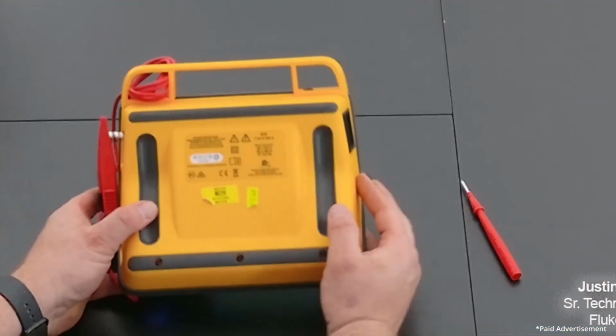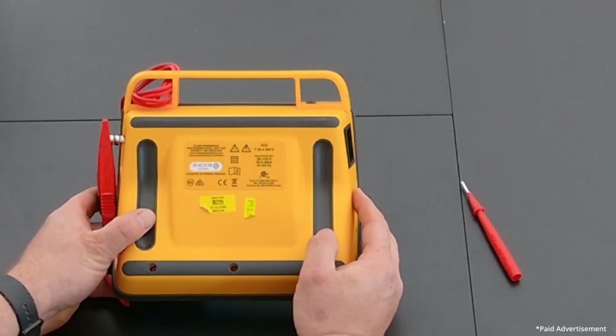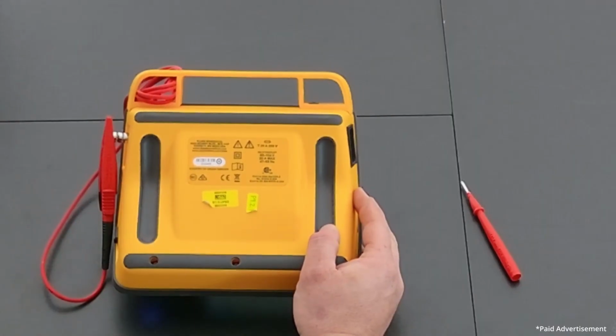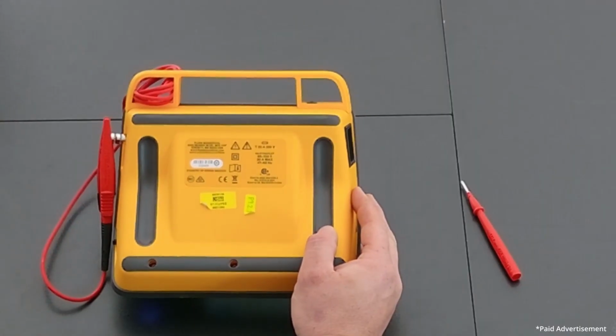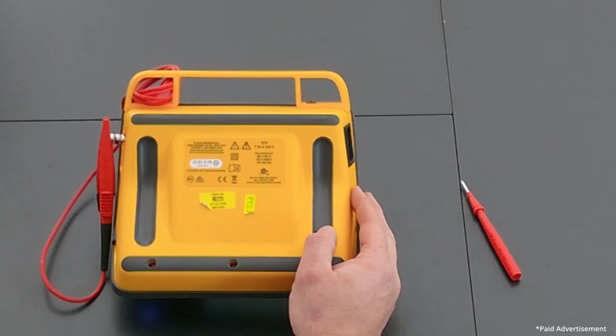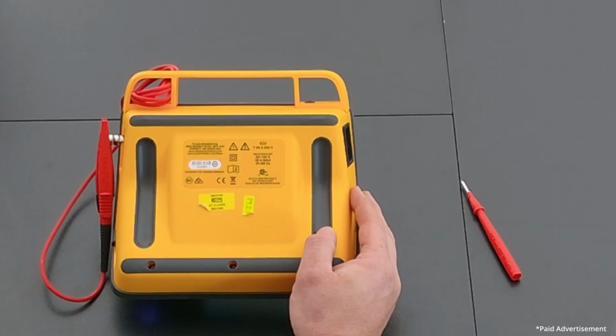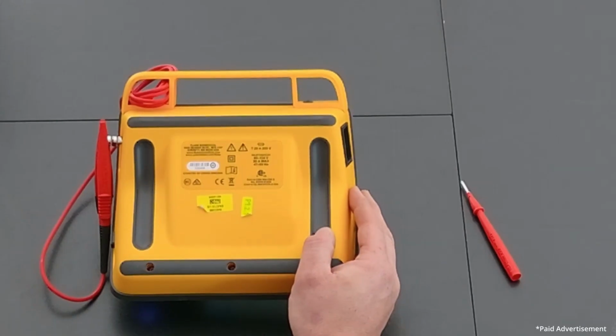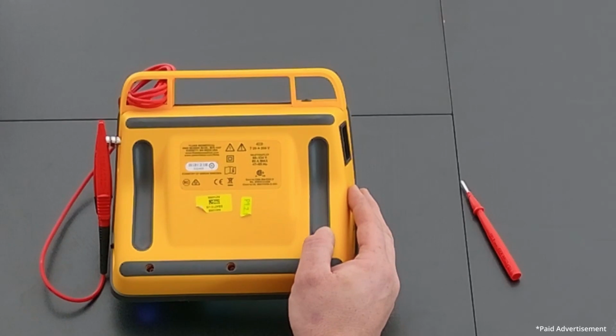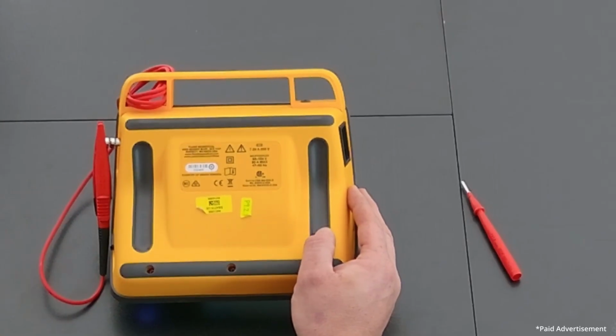I'm going to flip my safety analyzer over on the back. I'm going to challenge biomeds to flip over their analyzers, look on the backside, and see if they see a UL listing. Now, Danielle, I know the VAs are near and dear to you. If you look in your environment of care for the VAs or most healthcare facilities in the United States, it states that any medical device, or any device in your hospital, must be UL listed or higher. So flip over your device and see if you see that UL listing.